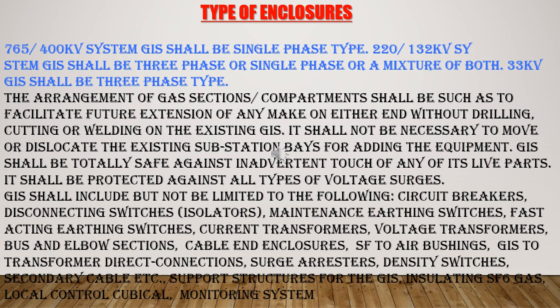It shall be protected against all types of voltage surges. GIS shall include but not be limited to the following: circuit breakers, disconnecting switches, isolators, maintenance earthing switches, fast-acting earthing switches, current transformers, voltage transformers, bus and elbow sections, cable end enclosures, SF6 to air bushings, GIS to transformer direct connections, surge arresters, density switches, secondary cable, etc. Support structures for the GIS, insulating SF6, local control cubicle, monitoring system.